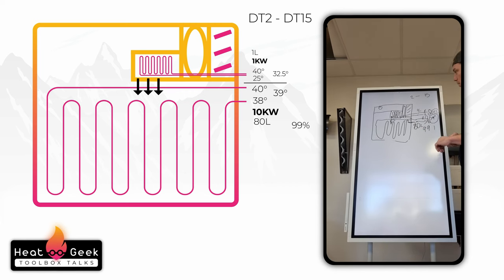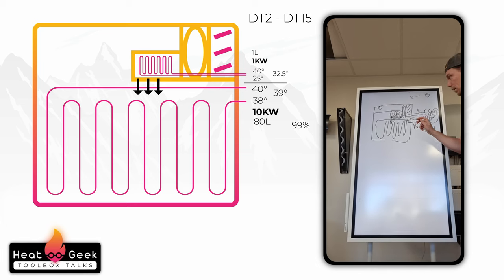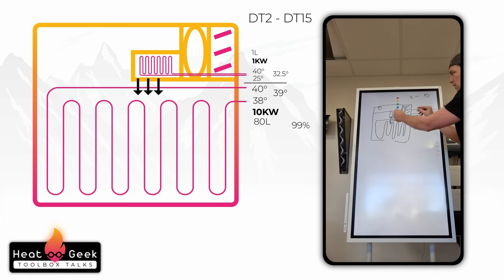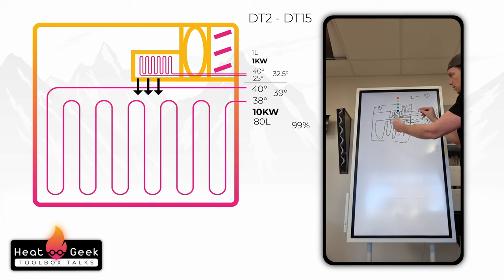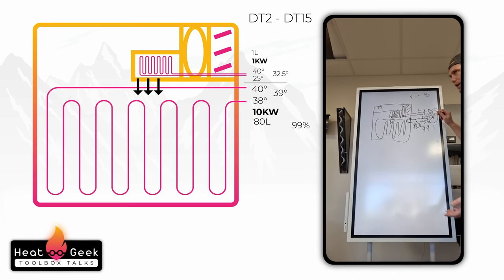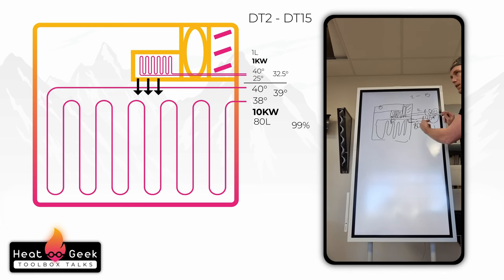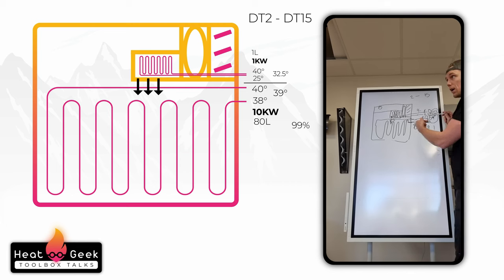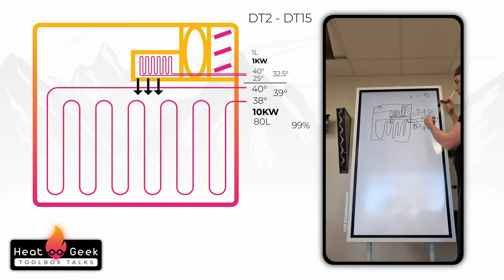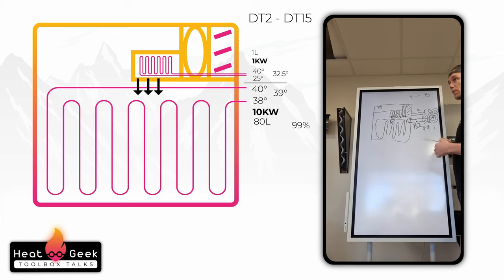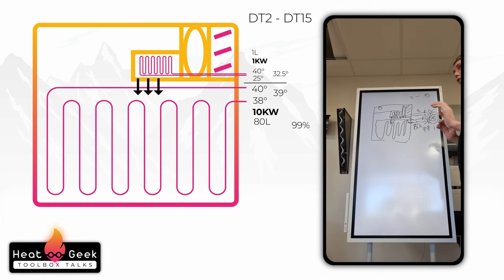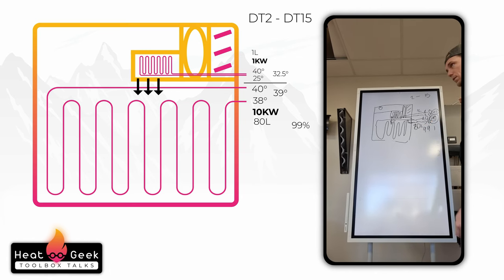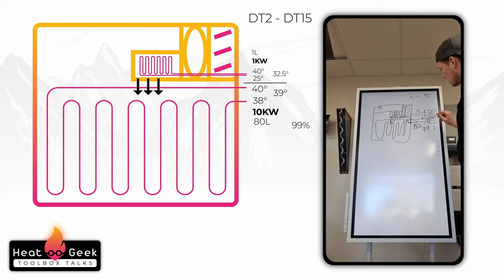That biggest room will dictate your flow temperature, but only relative to its DT. And its DT is relative to the smallest DT you need. So actually this kind of indirectly also dictates your flow temperature, because if we've needed a DT of two on this to make it work - it's an exaggeration, we didn't ever design this for a DT of two, we designed it for a DT of 10. They typically design for that even though we tried to design for a DT of five. But we've done DT2 giving 39 rather than 37, therefore the heat pump will come down two or three degrees and we'll literally get more COP. Once that mixes, that shouldn't mix anywhere though. Oh do you mean on the returns? Yeah, the returns - well you say that, the returns will mainly be this because you're mixing 80 to one liter, so it'll be a mixture of 25 and 38 but it will mainly be 38, it'll be 37.8.